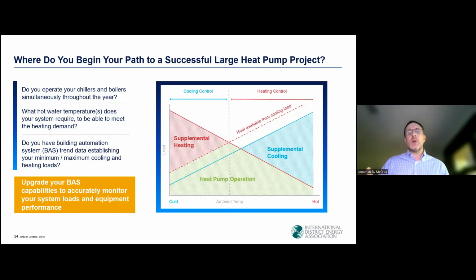Generally what you want to do is ensure that the heat pump is able to run 24/7, 365 all year long, without cycling off during its minimum load conditions. That's a key part of it, because you want to maximize the amount of savings that you get from it. And by the way, you may find that the optimal configuration is two machines instead of one. So I would say that's an important thing to evaluate.